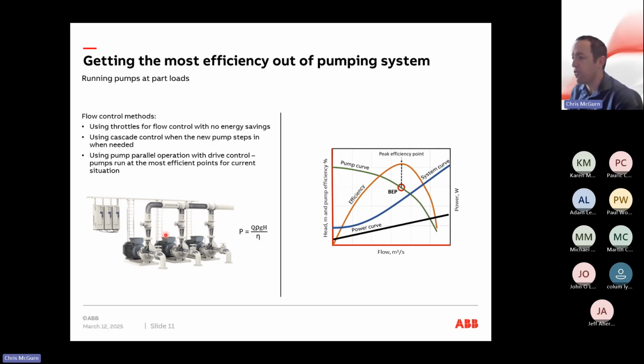Whereas if you were to look at electrically controlling that, through drives control, through a VSD, it means that you can bring the speed of the motor down without having to block the pump itself, which in turn brings the amps down and therefore uses less energy whenever it's running. So there is a benefit to electrically controlling the speed of the motor and the pump rather than doing it mechanically.